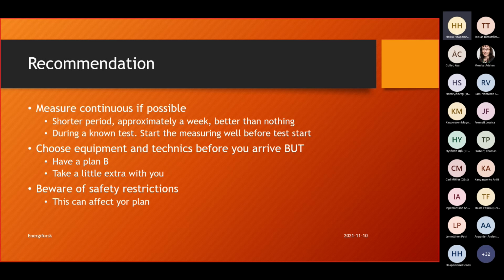So have a few different options. In a system we measure now, you can't measure with accelerometers directly on a valve, but accelerometers are better on the pipes. It's quite good, but on the valves we have to use seismic transducers because of the phenomena also talked about earlier, with high frequency sound or vibration. It depends on how you see it, but it's due to the flow. It's flow-induced sound and vibration with high frequency.